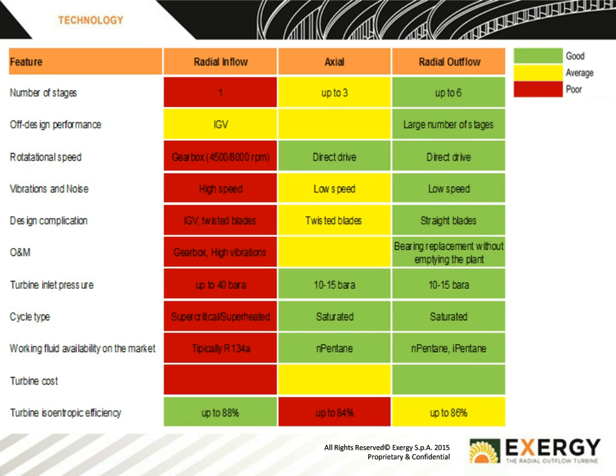And that really is unique in the market and has given us a great advantage in the plants which we have already installed. The next thing is the pressure of the cycle. Here both the axial and the radial outflow turbines have the advantage of a low pressure cycle. A low pressure cycle means less expensive valves, simpler piping, and simpler maintenance moving forward. Again, now we talk on to different cycle types. And again, this saturated cycle is a low pressure, simple cycle, which generally is easier to operate.